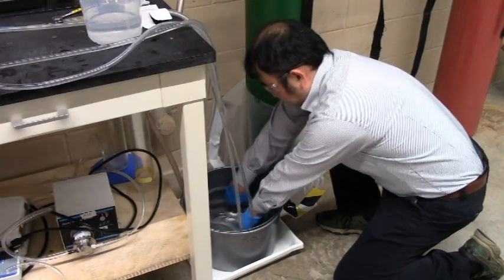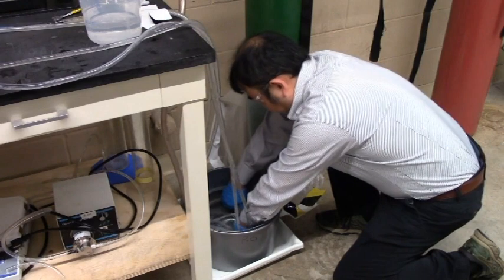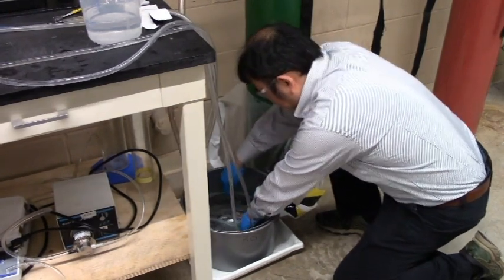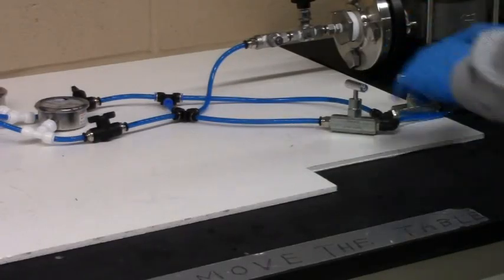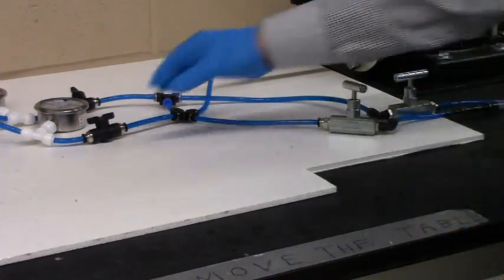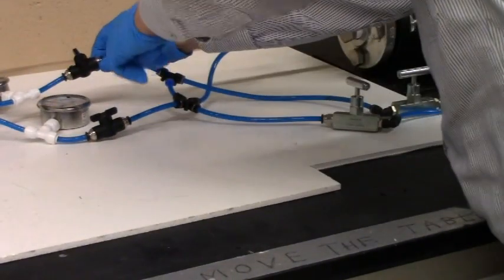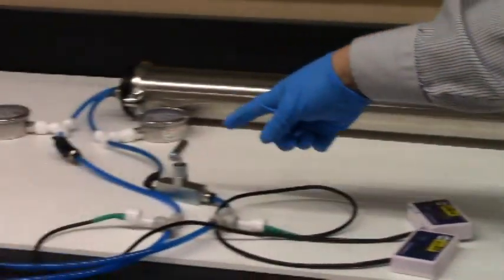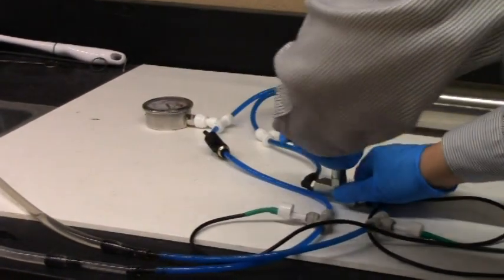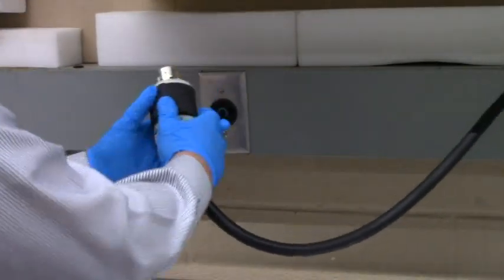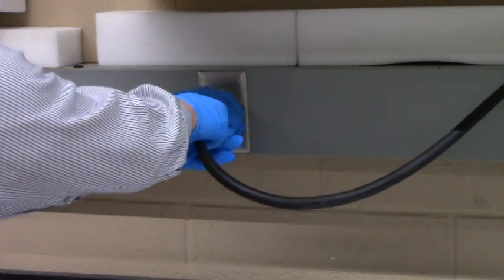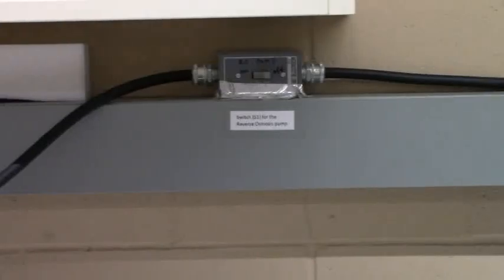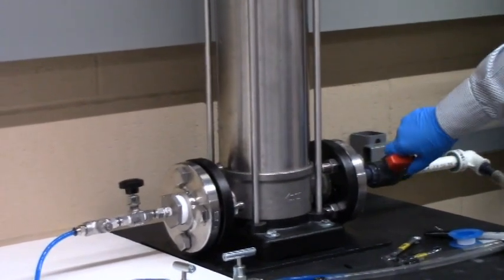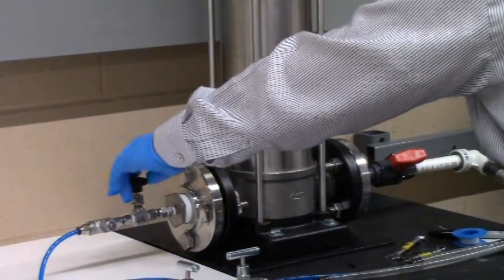Attach the yellow filter to it underwater and make sure the yellow filter lies flat on the bottom of the bucket. Make sure the filter inlet valve and two bypass valves are open, while the back flush valve is closed. The two valves after the filter housing should be fully open as well. Plug in the electrical plug of the centrifugal pump in the special wall outlet. Turn on the pump by flipping the switch, and you will hear a loud noise of the pump motor. Open the pump suction valve and then pump discharge valve.